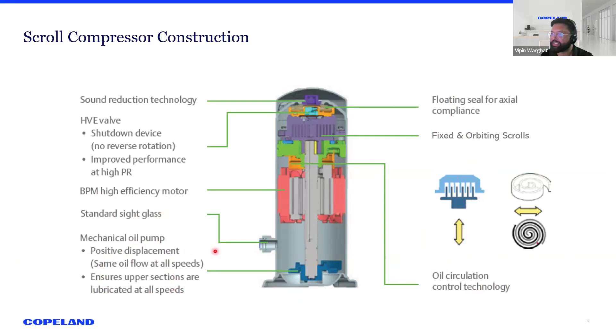There are various safety and lubrication devices, including a positive displacement oil pump that ensures sections are lubricated at all speeds, a floating seal for axial compliance needed for the scrolls to move freely, and oil circulation control technology to ensure proper lubrication in the scroll.